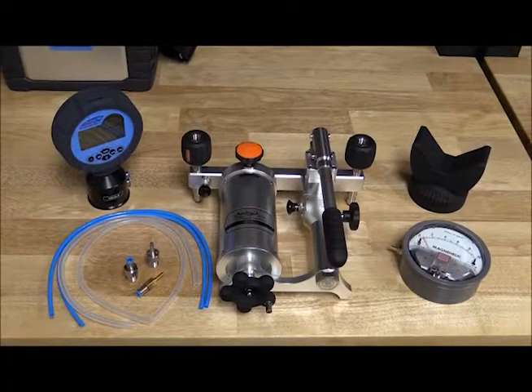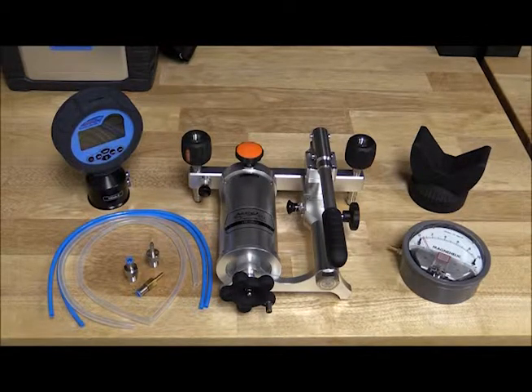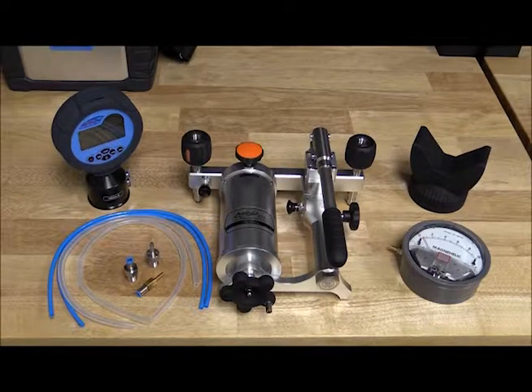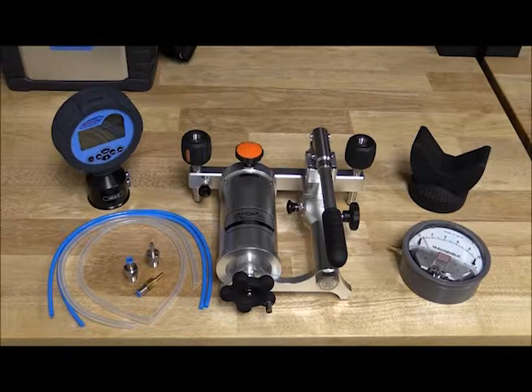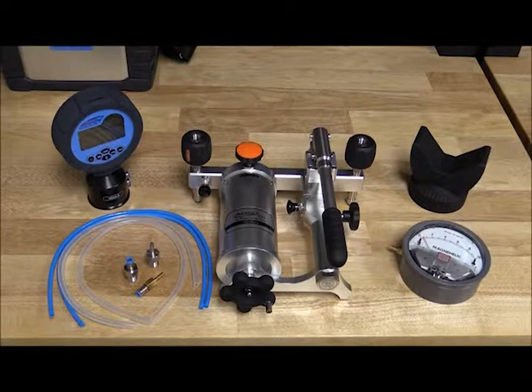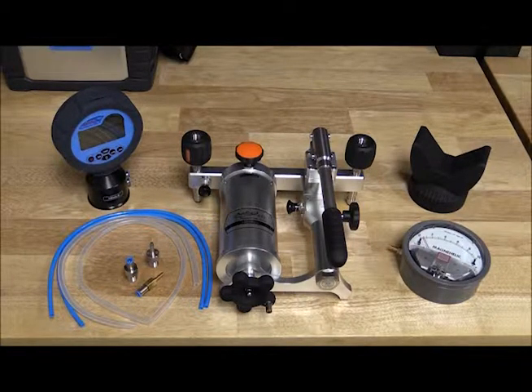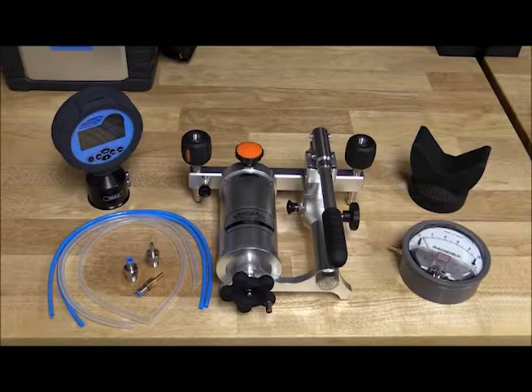In this example, we will use an Additel 912 pump to generate the pressure. The 901 pump could also be used. However, the 912 is better able to handle higher ranges and higher volume instruments for this type of setup. The Additel 681 differential gauge will be used as our accurate reference, and we will be calibrating a magnehelic differential pressure gauge that is 0-10 inches of water.